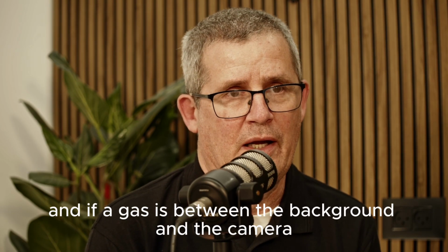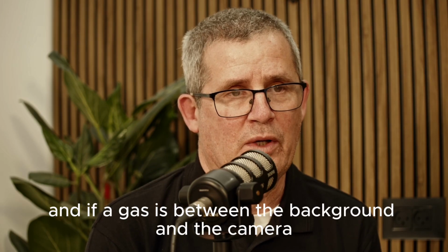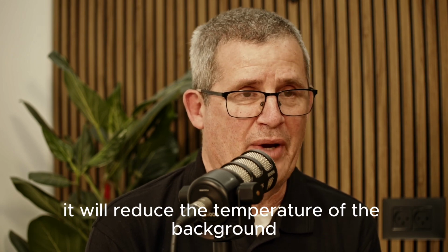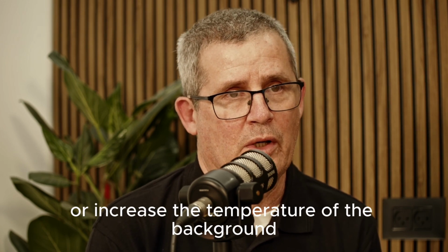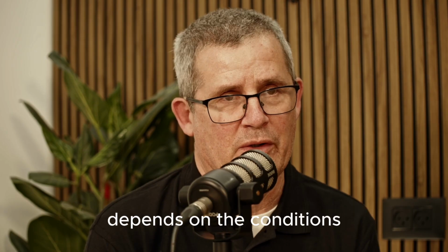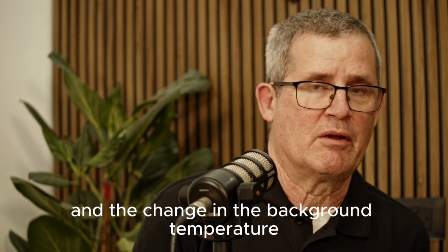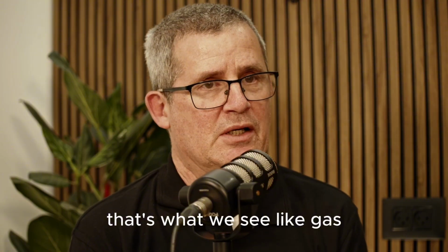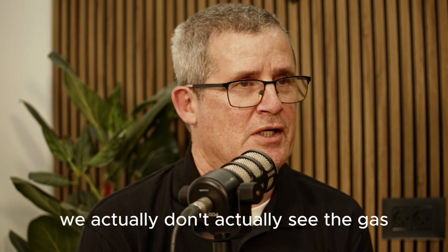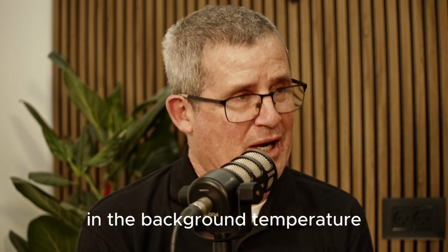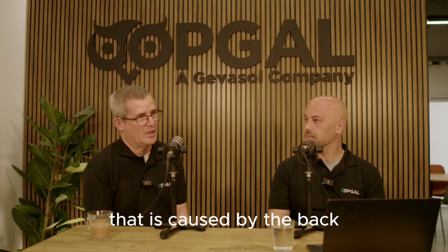If a gas is between the background and the camera, it will reduce or increase the temperature of the background, depending on the conditions. The change in the background temperature is what we see as gas.